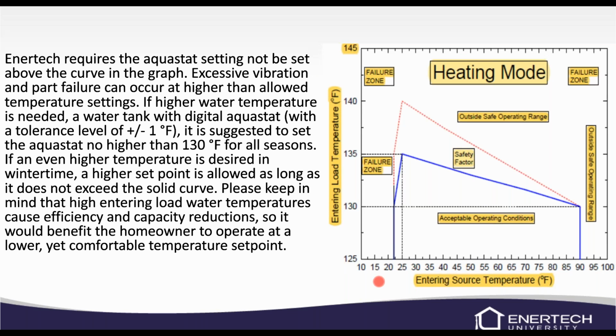So in our IOM, we do list a safe operating range for the variable speed compressor. We need to make sure that we're staying within this blue operating range of acceptable. Now we do have a little bit of safety factor, but when we start getting out of this range, this is when we have compressor failures. So we could get lots of vibration, part failure, refrigerant leaks. So we want to make sure that we do not get too high a water temperature. You can see that the max we're going to be at is 135. So outdoor reset is going to make a lot of sense to help save the compressor and make sure we're always following along with this chart here. There's one for heating and there's one for cooling as well. That's listed in the IOM.